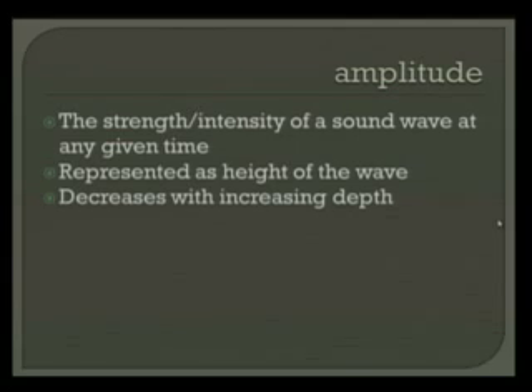As you know, the amplitude of a wave as it comes through 2, 4, 6, 8, 10, 12 centimeters of body tissue gets attenuated, right? The amplitude goes down. So to compensate for this, we have something inbuilt in our machines, and that's called the TGC, the time gain compensation. So this is very important for us to know. All ultrasound equipment is based on the premise of the time gain compensation.